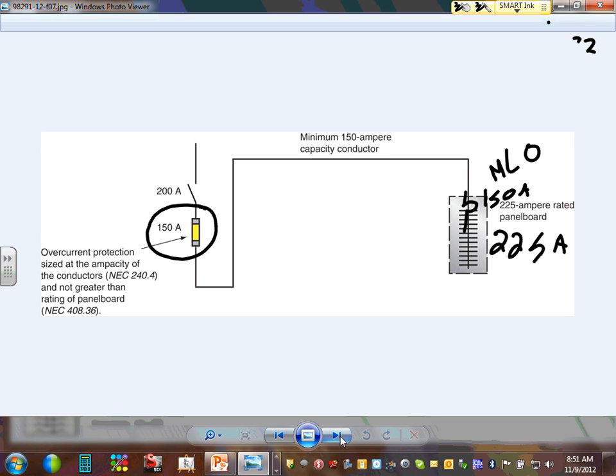Okay, that's a good point. Well, first of all, if I put it here, do I still need another one here? Yes, because you still need to protect the feeder. Number one, if you bring that fuse here, you still have to have another fuse here to protect the feeder. So by putting it here, you saved yourself a fuse or a circuit breaker. That's why main lugs only, people love them. Another advantage of putting the circuit breaker here is arc flash. If you have an arc flash right in this panel, the fuse is protecting you from the arc flash. If you put the fuse right in here, the arc flash has to be based on the rating ahead of the fuse. That's another advantage of having the fuse outside.